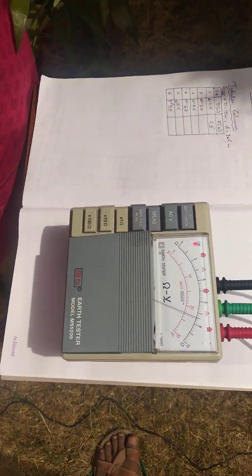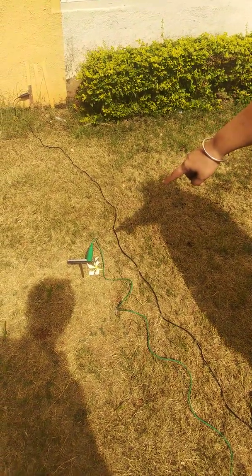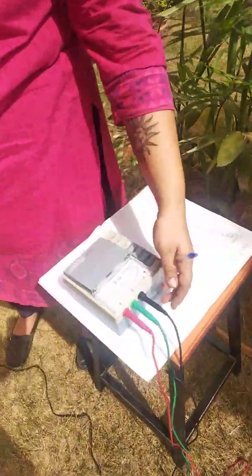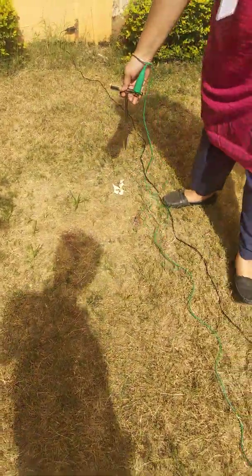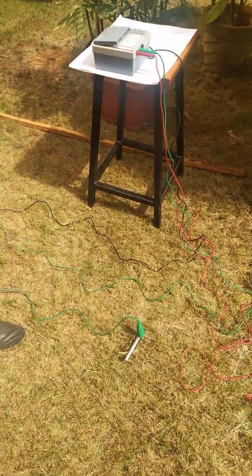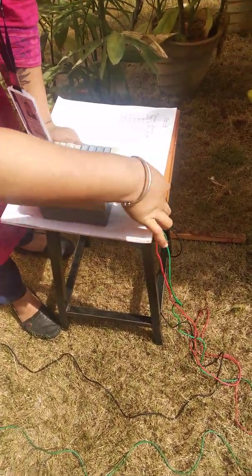The first reading is done. To take the second reading, we need to move the P electrode — the potential electrode — from its first position to the next position. Before touching the electrode with bare hands, switch off the megger kit, disconnect the black terminal, then touch the earth electrode by hand and move it to the second point. The distance between the earth electrode and the P electrode will now be three meters.